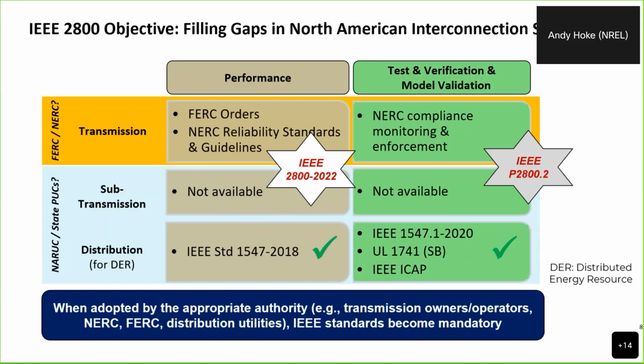But as I mentioned earlier, none of these standards are mandatory when published by IEEE. They only become applicable, and we only see any benefit out of them once they're adopted by the entities that are in charge of interconnection requirements. So right now, 1547 is going through this process of being adopted by distribution operators and their regulators. And then we're kicking off the same process for IEEE 2800 right now.